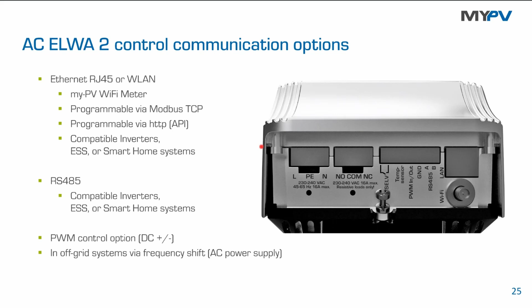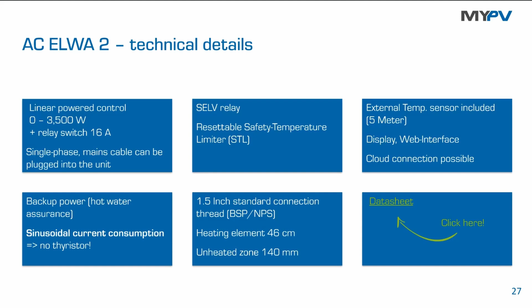All right, benefits - I think I already mentioned that. One important thing for both units, ELWA and AC ELWA-2, is that it's possible to install them in hot water boilers or in storage tanks. In storage tanks, they can also support a hydronic space heating system if you like. The only thing to consider is that we recommend not going above 60 degrees centigrade when in contact with fresh water in hot water boilers, because calcification can also be an issue for our immersion heaters. As always, in space heating water in a storage tank it does not matter - you can go up with the target temperature to the maximum if you like, and support the hydronic space heating as much as possible.